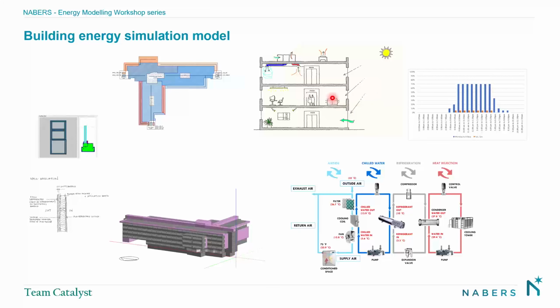The thing to point out is that when you look at people loads, you have two or three things to consider. People generate heat. All of us are equivalent to about 100 to 130 watts of continuous heat generation. So the number of people in a space matters. With the people, you have to provide ventilation air. Otherwise, you risk people getting lethargic and, worst case scenario, suffocating. But that is again dependent on people. And for people, the heat load that we generate is not purely sensible load. We also generate some latent or moisture loads that the air conditioning system needs to take care of.